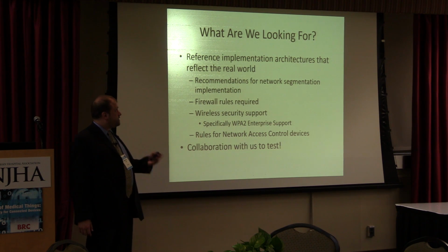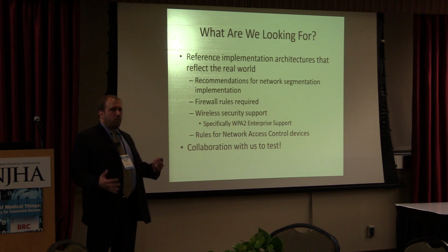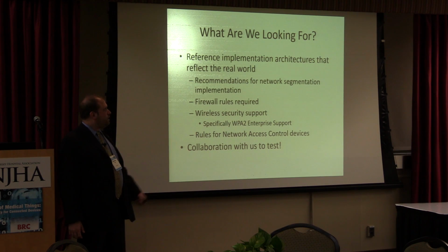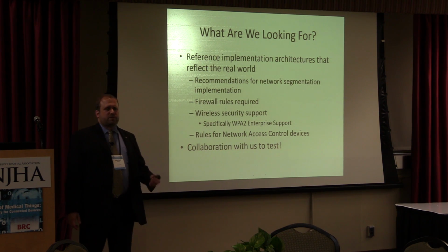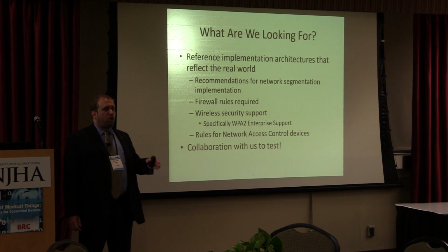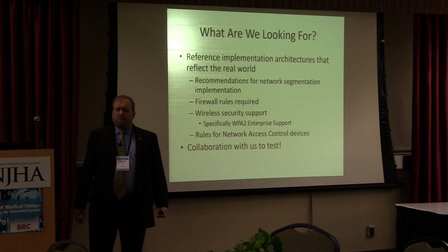Reference implementation architectures that reflect the real world. So we want to hear from the vendors. What are your recommendations for network segmentation implementation for your device? What are your firewall rules? In other words, how can we put this on our network with its own little walled garden so that we can protect it from the rest of the real world? Because the real world in the hospital is kind of rough.